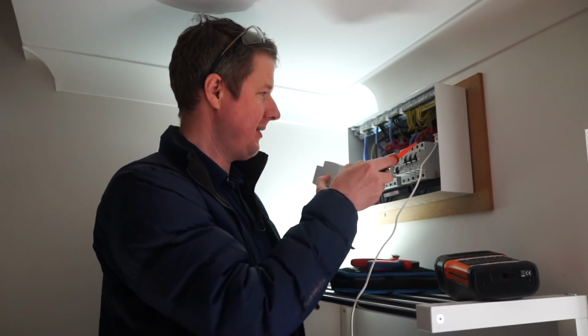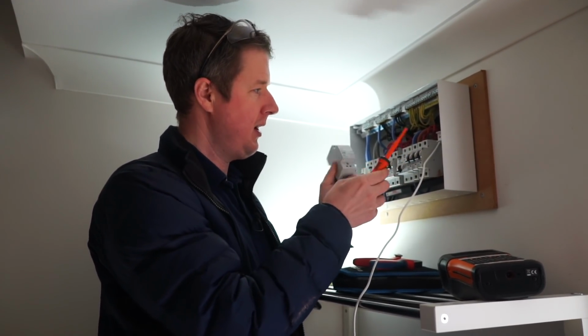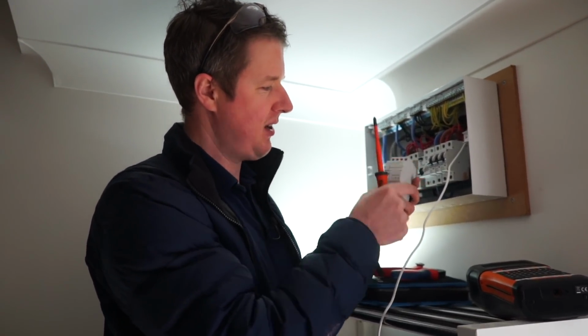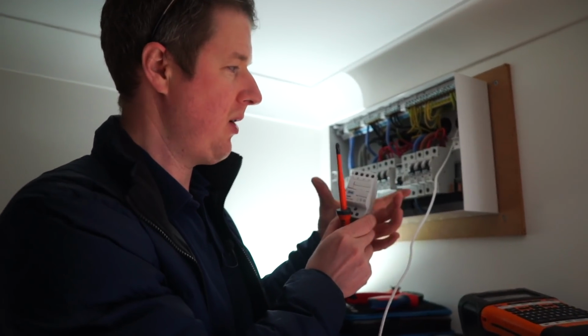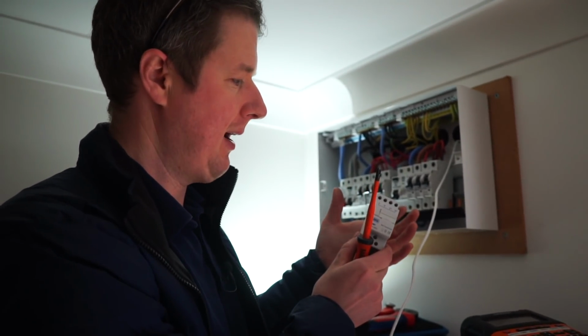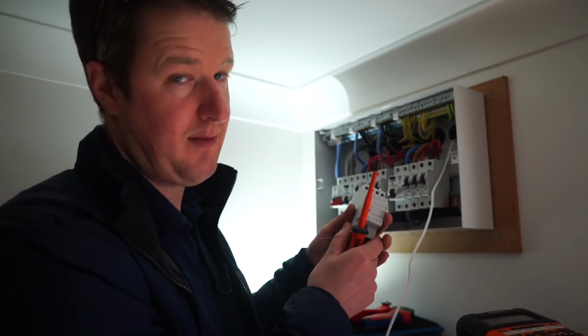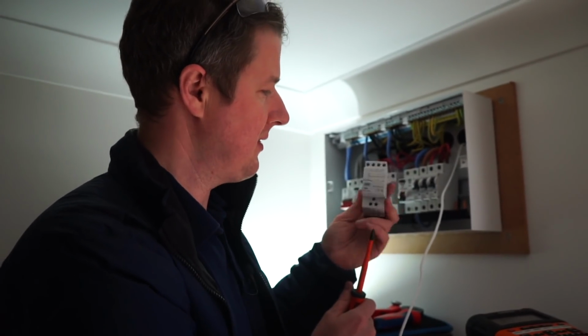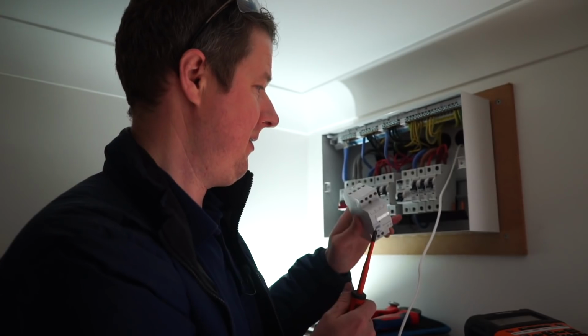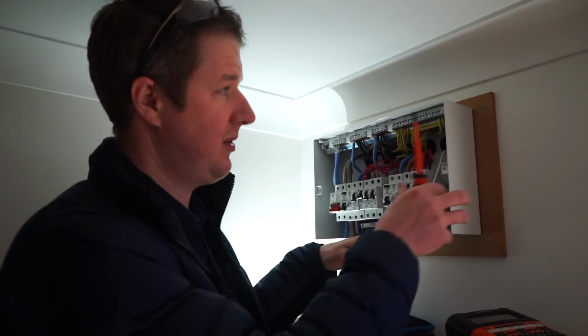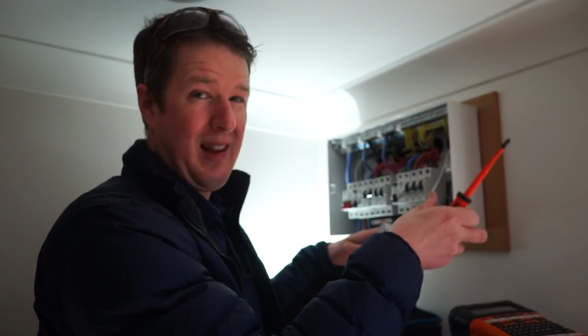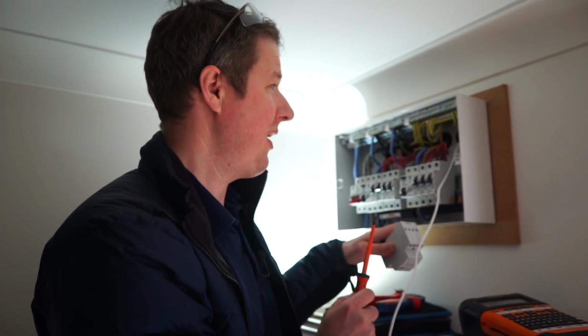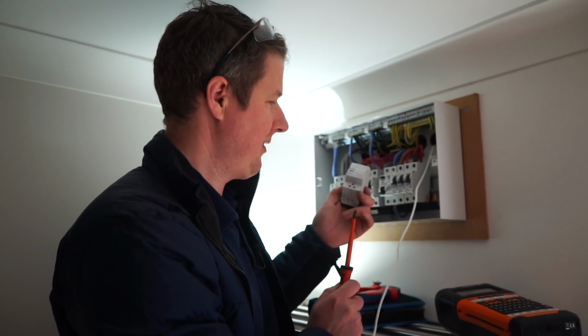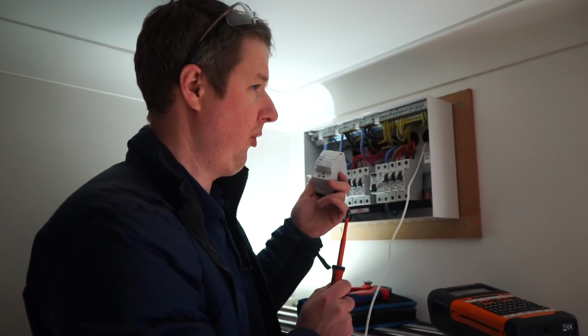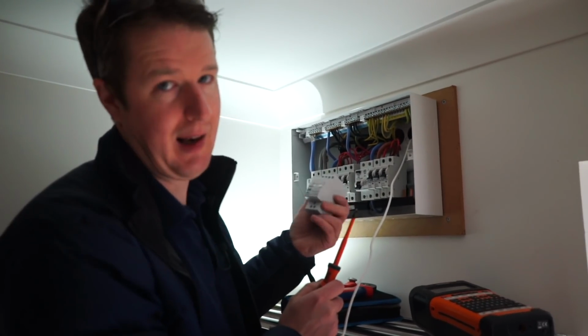What I'm going to do is shift these across so I've got a little bit of space next to the transformer as well, so it's got space both sides for the heat to dissipate. The only way to install this without putting it in the consumer unit enclosure would be to install another enclosure next to it, and I just think that's a bit over the top. It's not really necessary, and it's very unlikely this is going to cause any problems for not being type tested - it's just a technicality basically.